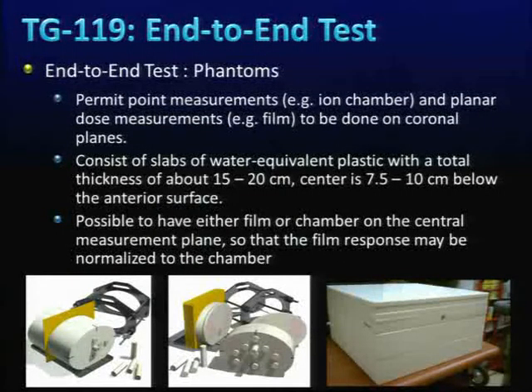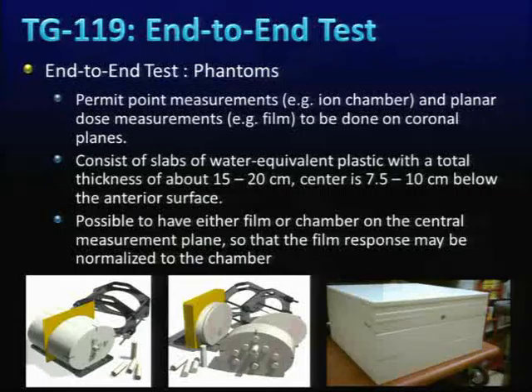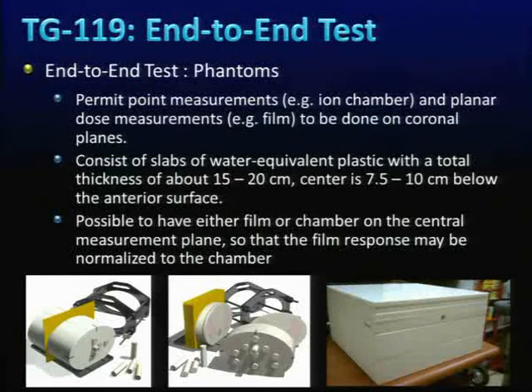TG-119 specifies requirements for phantom type and measurement methods. The phantom must permit point measurements with planar dose measurement, for example using film. Phantoms should be water-equivalent plastic slabs with total thickness greater than 15 cm, and the center should be 7.5 to 10 cm below the anterior surface. Film and chamber can be used together to normalize film measurements to absolute dose from the ion chamber.